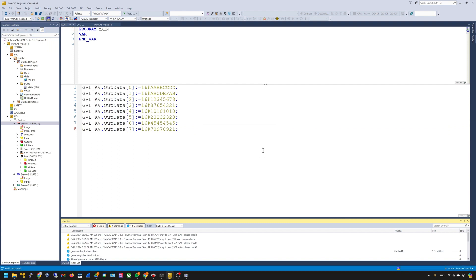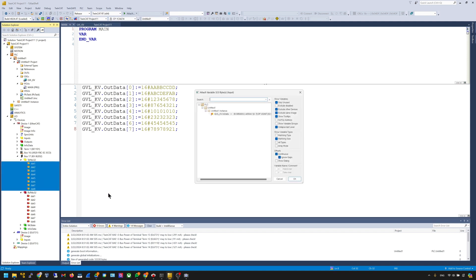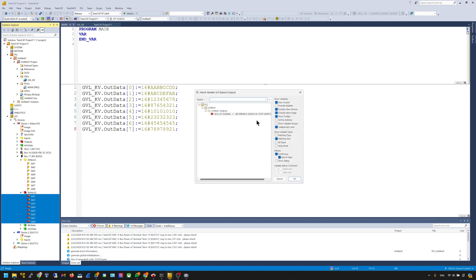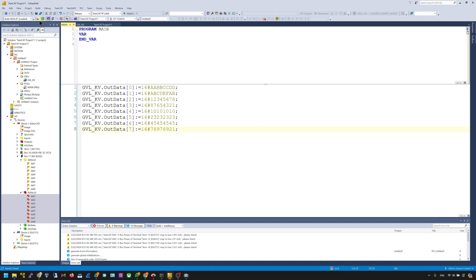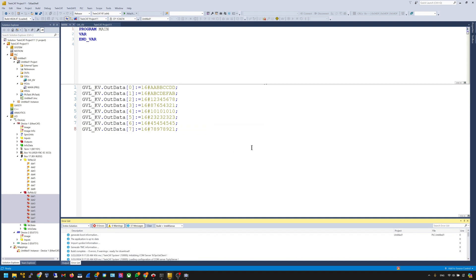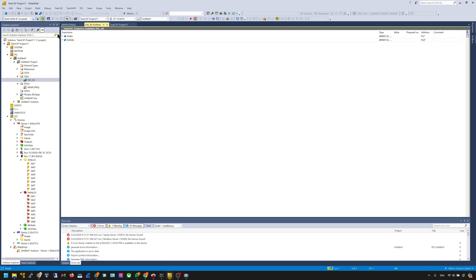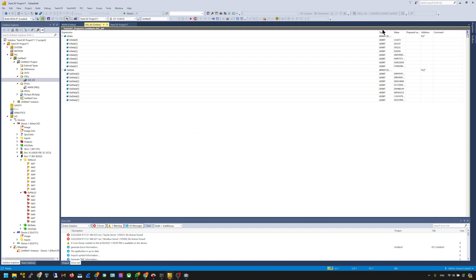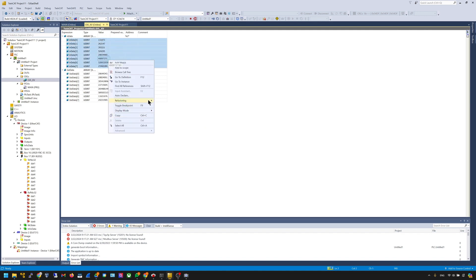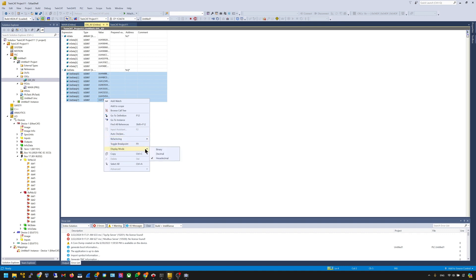Then we need to build the project — go to Build, Build Solution. After the build, we can map the data. Go to the Input, open your input and output data, select all, right-click, choose Change Multiple Link, and select the data defined in the GVL. Do the same operation for the output. Save it, and then use Activate Configuration to download the project to the IPC. Switch to Run mode, and we can log in.